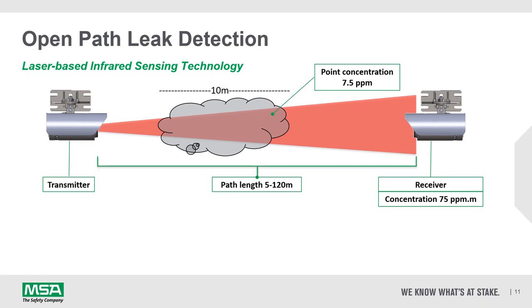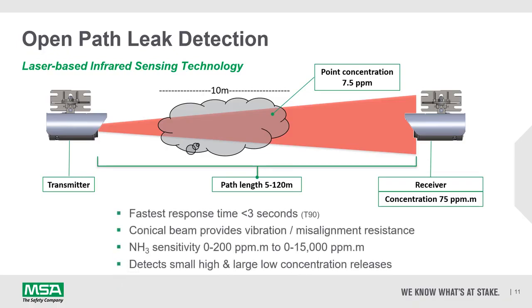That's 10 times 7.5. This technology is probably one of the fastest for the detection of ammonia, with a response time of less than 3 seconds. The conical beam allows and compensates for either misalignment or vibration, and has a sensitivity of 0 to 200 out to 0 to 15,000 ppm meters, so it can detect small high concentration gas clouds or large low concentration gas clouds.